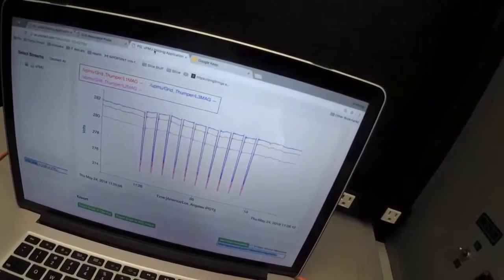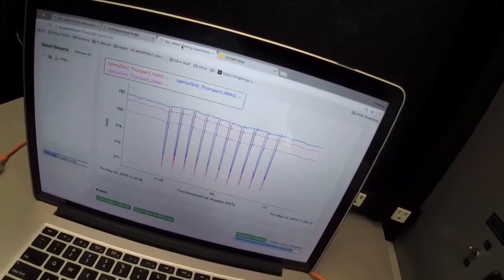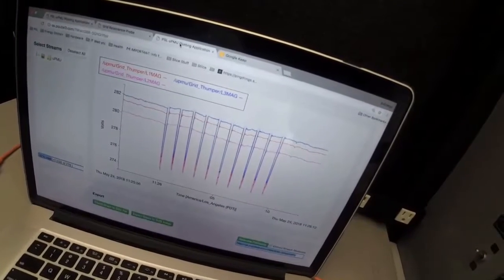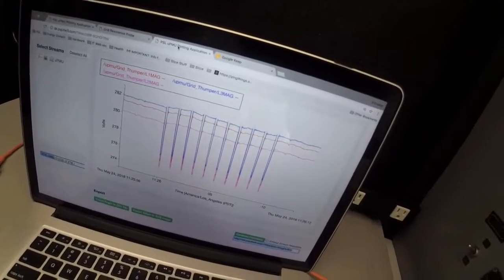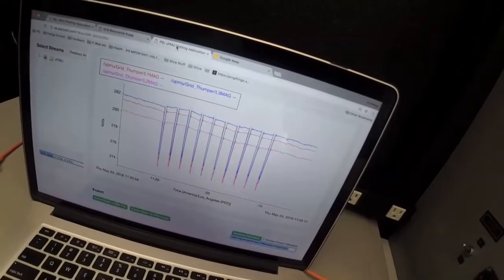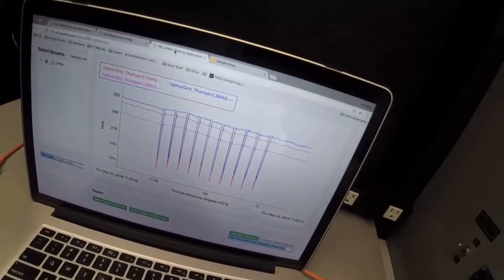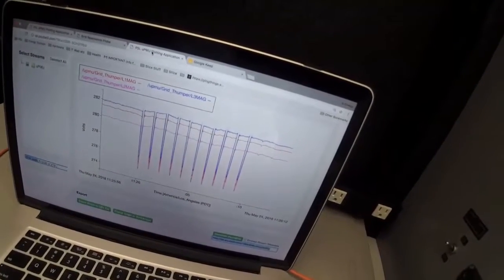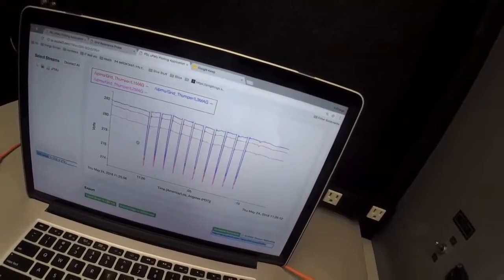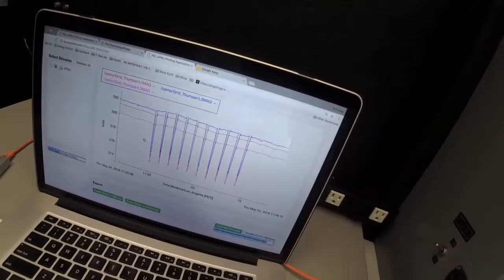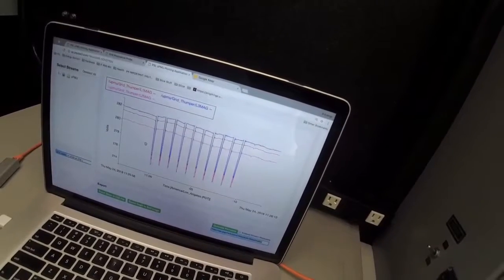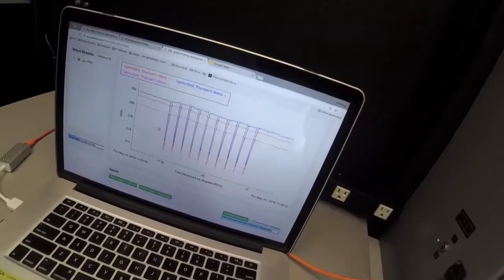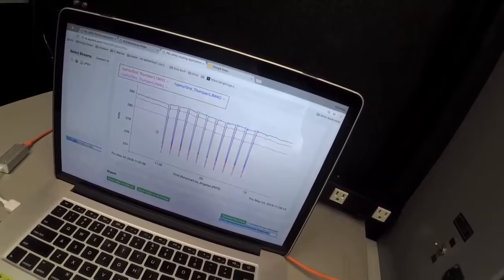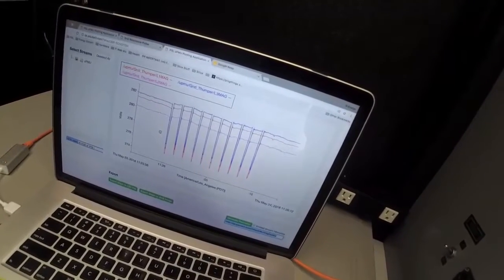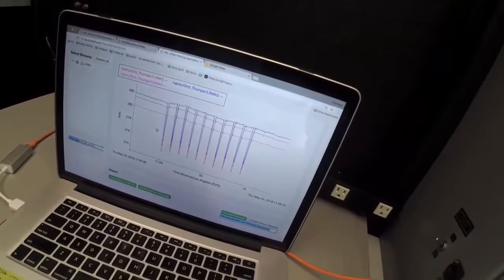This is the measured results from that test. You can see the voltage actually drops locally at this site due to the power flow we just caused. Each phase responds a little differently. Proportionally, it looks like we're dropping about 6 to 8 volts at this site, and this is one of the indicators of the inductance upstream from this device.